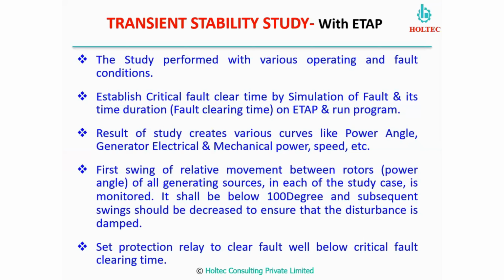So when we find out, for that particular generator or all of the generators, the least possible fault clearing time that ensures stability, that is my critical fault clearing time. And now we have to ensure that our protection relay is set well below that fault clearing time, so that our entire system will be stable for any such transient.